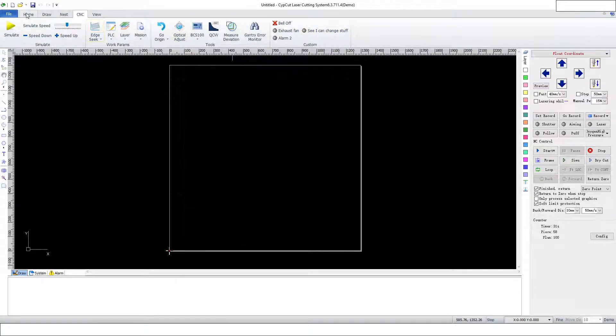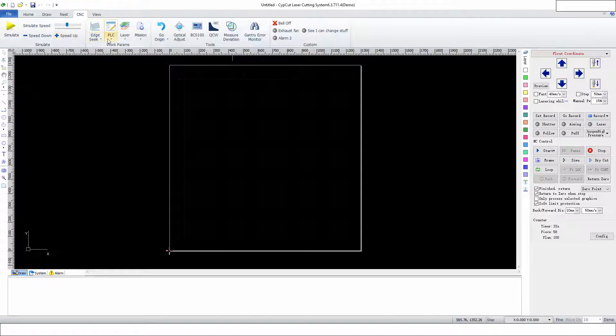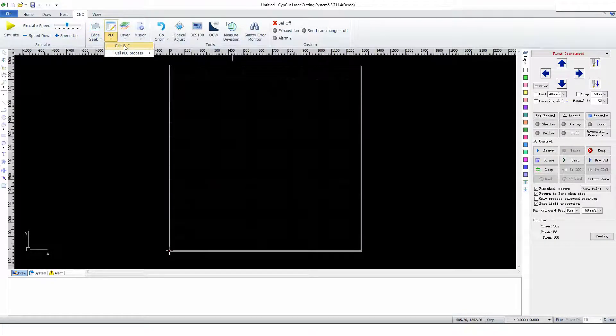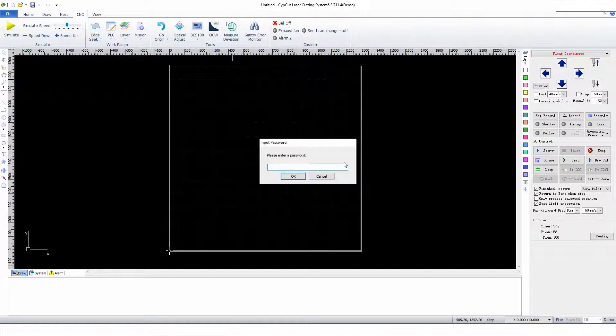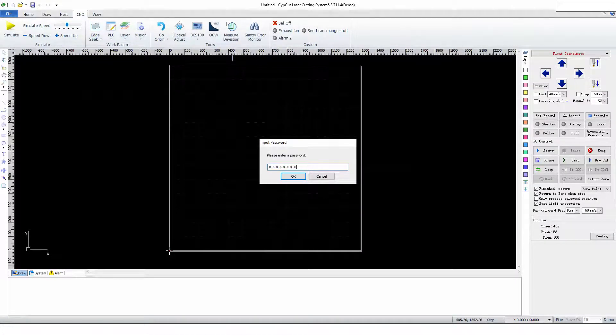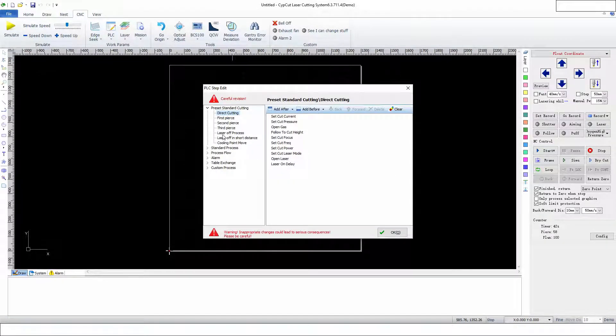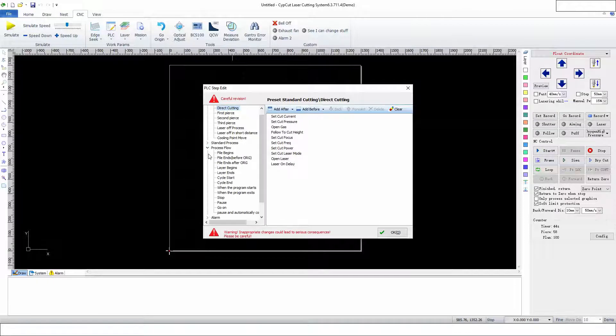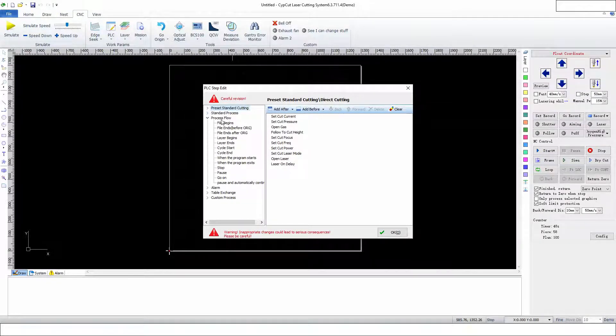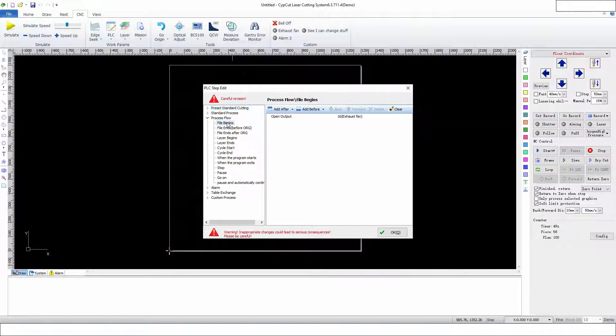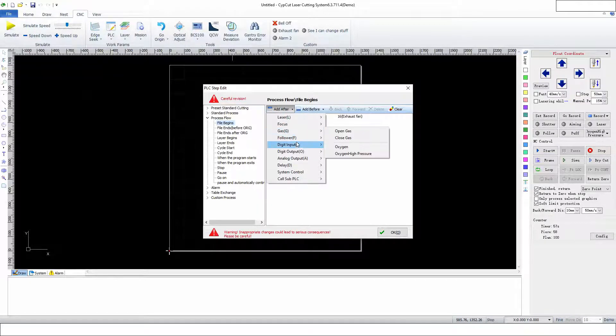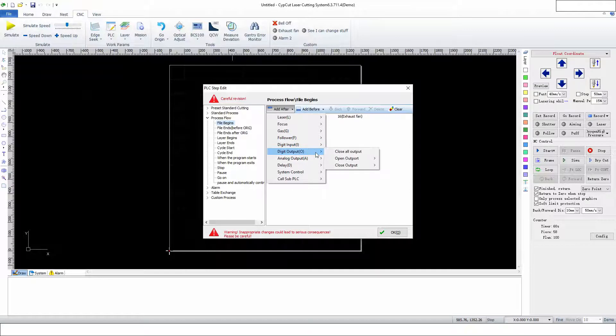Or we'll have it turn on while it's cutting and turn off, whichever. Let's go Edit PLC. We have to type our password in again. Generally, you're going to modify things in Process Flow; at least that's where I find it useful. We're going to go to File Begin and add after. This is going to be when I press the start button, it's going to do this.